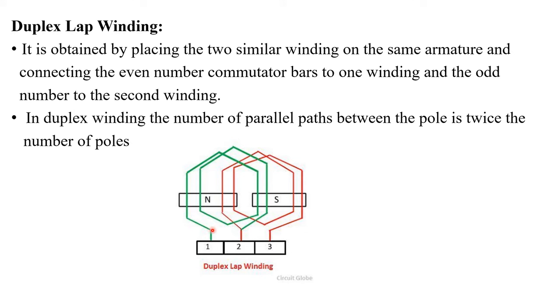In duplex lap winding, which is obtained by placing two similar windings on the same armature and connecting the even-numbered commutator bars to one winding and the odd-numbered to the second winding. In this diagram you can see duplex lap winding. This green colored coil will start from commutator segment 1, wound like this, and this region will not directly enter the second commutator segment — if it did, it would be simplex lap winding. Instead it continuously winds and then enters the second commutator segment. Here you can see four parallel paths in the green colored coils.